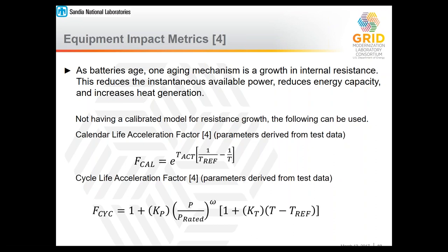Generally, each manufacturer will have a very precise model for how this impedance grows over time. They'll have a calibrated model associated with the exact mechanisms for that behavior. But because those are usually proprietary, and we don't have access to those, we do have a couple of acceleration factors to use from one of the references. And that is calendar life acceleration factor and cycle life acceleration factor.